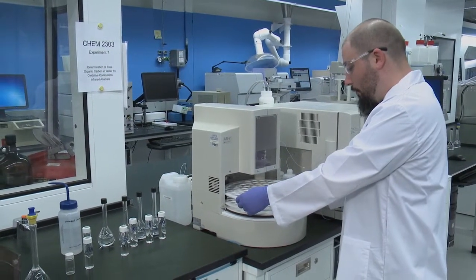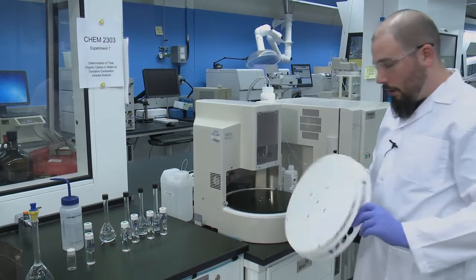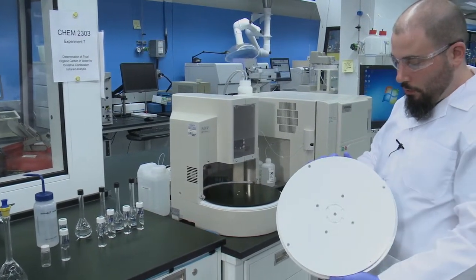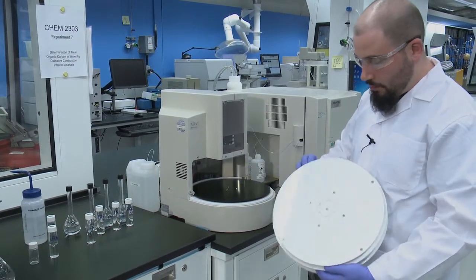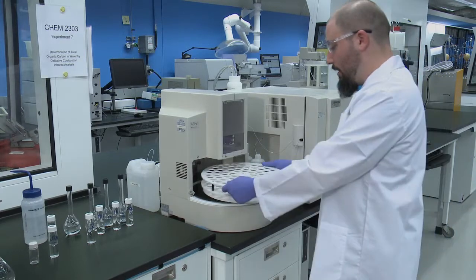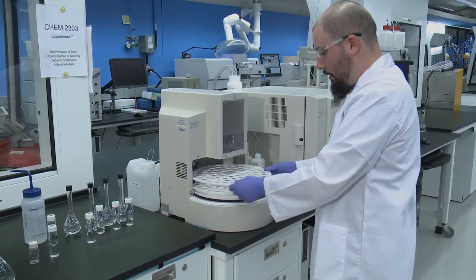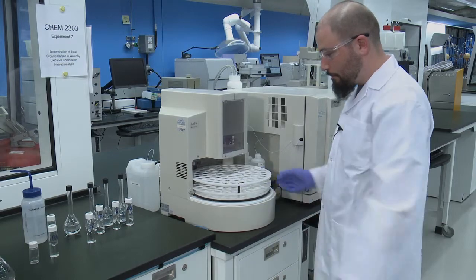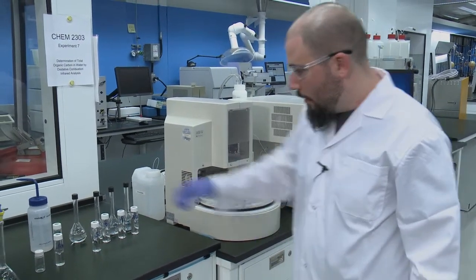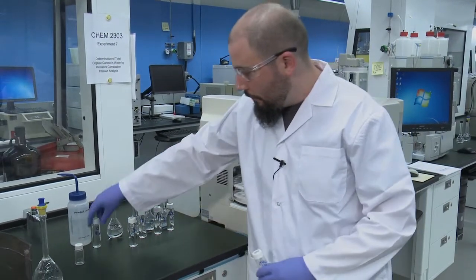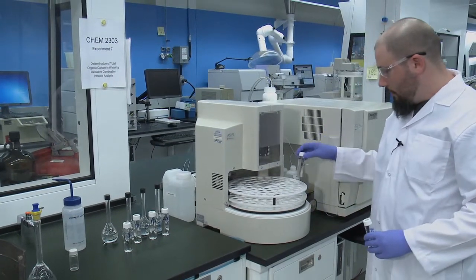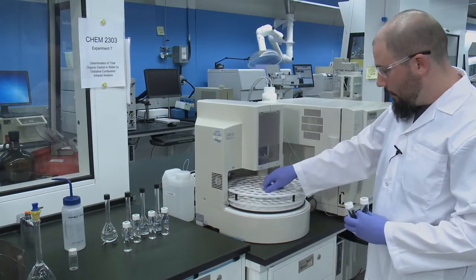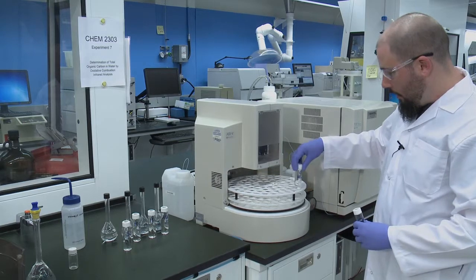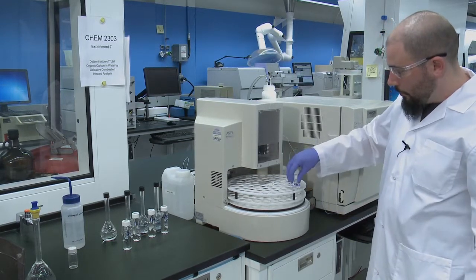And you can remove this tray if you want. On the bottom are registration holes and three pins. So when you're placing it back in the device, ensure that you turn it until it sits on those pins. Then you want to place all of your vials into the tray, taking note of what number you're putting them all into.